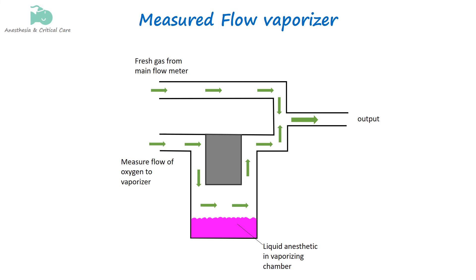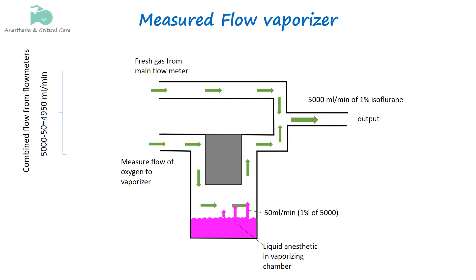Adjusting the vapor concentration with this method is a complex process. Let's briefly try to tackle it here. Let's create isoflurane at 1% with a total flow of 5 liters per minute. To create this mixture, the vaporizer must generate 50 milliliters per minute of vapor, which is 1% of 5000. So 1% isoflurane in 5 liters per minute flow requires 50 mL/min of isoflurane vapor diluted in a total volume of 4950 mL of fresh gas. The 4950 mL/min is the combined flow from the two flowmeters.